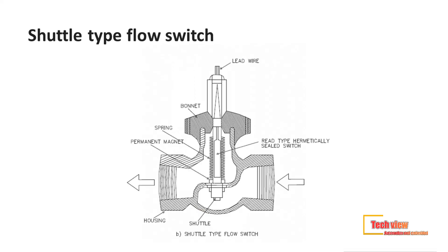Next is the shuttle type flow switch. Shuttle style flow switches operate because of DP or the velocity of the liquid acting on a disk. On the concept of a moving force, a shuttle at the bottom and a magnet just above the disk are connected to the disk. The shuttle body's upper part spindle is working against a spring of compression or gravitational force.